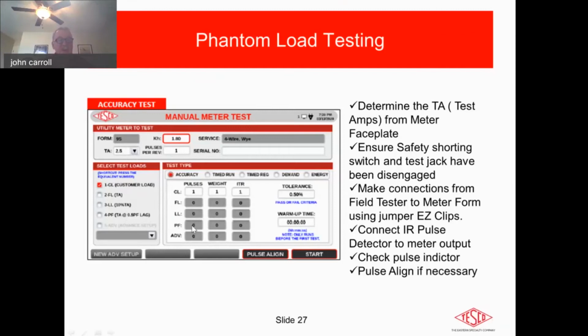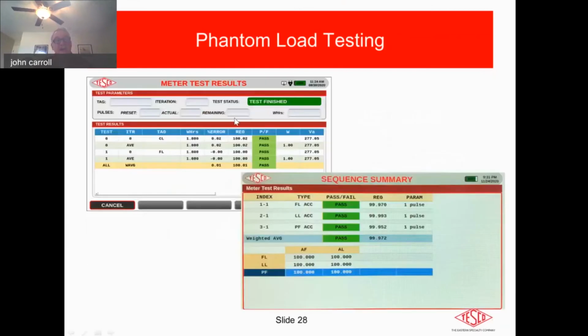When you go to do the power factor, you now have full load again, which is 2.5, but now your power factor has changed to 0.5. So again, it might be 1, 2, or 3. So you can vary this around, but when you do that test, hit start, this is the sort of screen that you'll receive. And you can see here, there are 2 examples. In this case, on this sequence we did, we can see a full load accuracy, we can see a light load accuracy, and we can see a power factor.